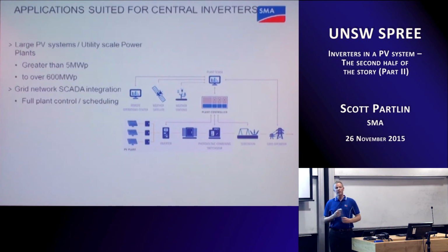Every single inverter that's ever connected to the grid needs to be able to detect when there's an island. So it needs to be able to detect when the grid that it's connected to has stopped operating. Maybe there's been a power blackout or there's been a fault on the network, and at that point they need to turn off. When you start to get to utility scale or very, very large PV plants, they can represent a very, very large proportion of the power on that grid. And so their ability to detect faults elsewhere in the grid becomes much more limited.